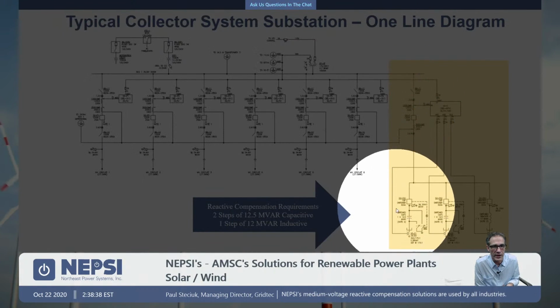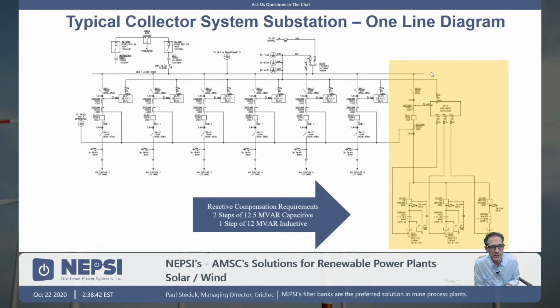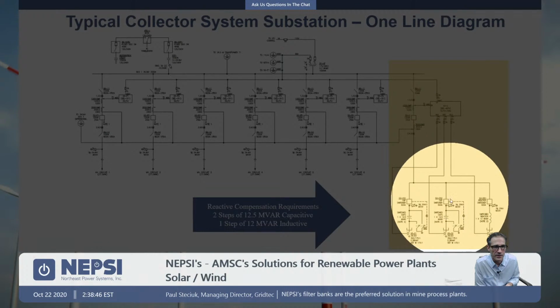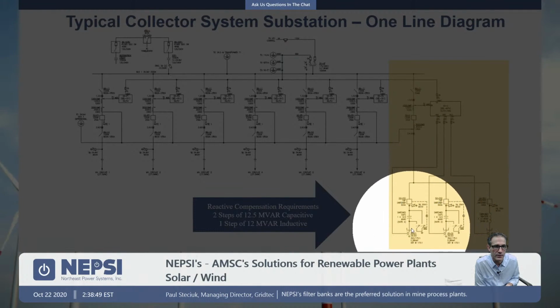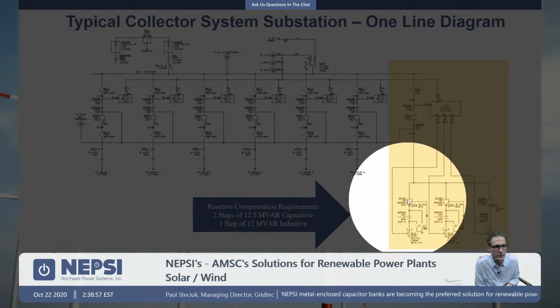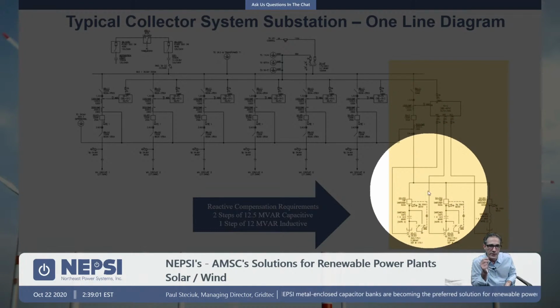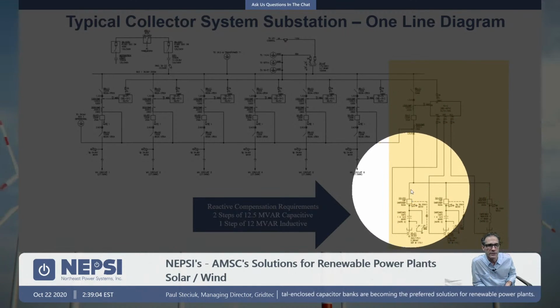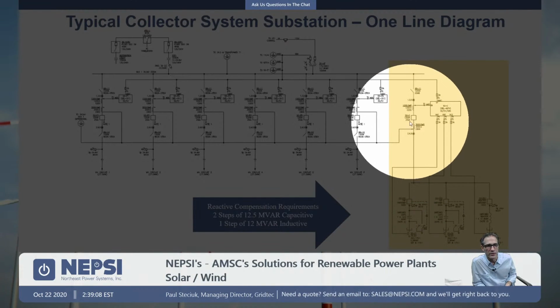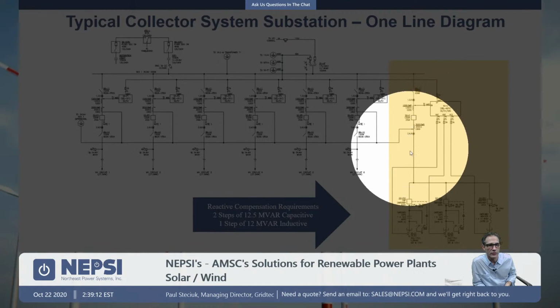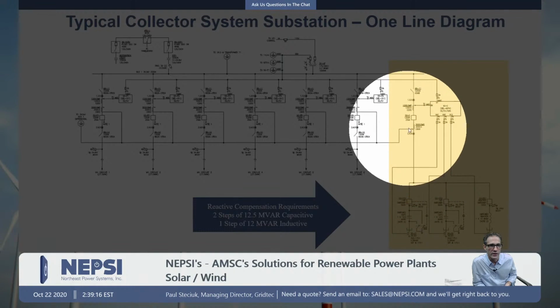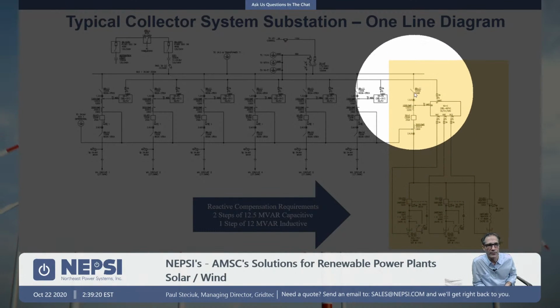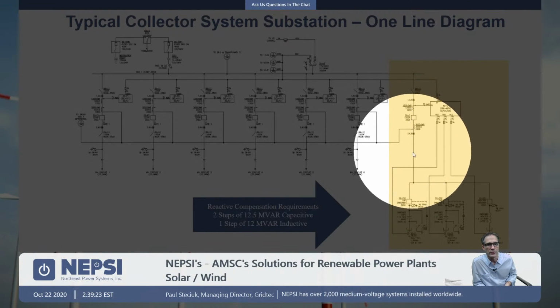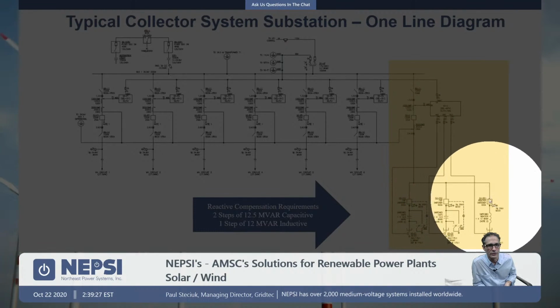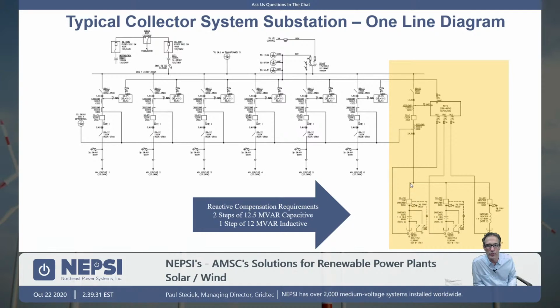So the shaded area represents the reactive compensation for this project. On this project, there were 2 capacitor banks located here. These are the switching devices. So you've got the cap bank here, and you see there's a neutral CT or a neutral PT, cap bank, switching device. Again, that switching device could be a Southern States cap switcher, or it could be a VD4 or VD4CS. And then up here, there's a breaker. This is a feeder breaker. This feeder breaker has to be installed because if there's a fault down here within the capacitor bank, you've got to have short circuit protection. And then you have a gang operated switch here. So gang operated switch, feeder breaker, supplying 2 capacitor bank stages and 1 shunt reactor stage. That's the design requirement for this project.